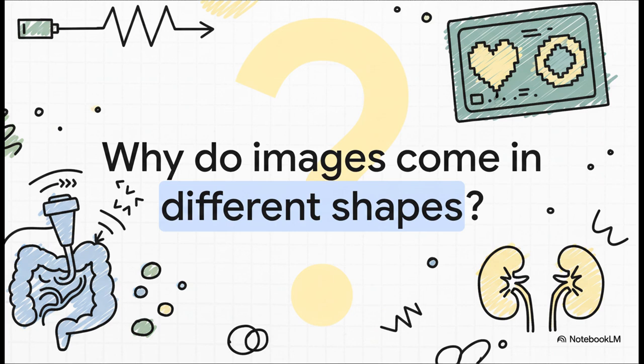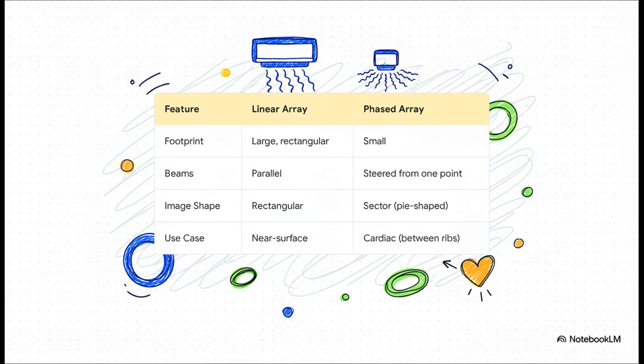So you've probably noticed that not all ultrasound images look the same, right? Some are rectangular and others are shaped like a wedge or a slice of pie. Well, that's not just a style choice. It's determined entirely by the design of the transducer and the specific job it needs to do. Let's look at the two main types. On the left, you've got a linear array. It has a big, flat surface and it sends sound beams straight down in parallel lines. That creates a nice, wide, rectangular image, which is perfect for looking at things just under the skin.